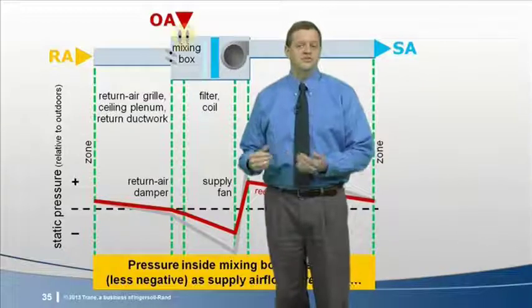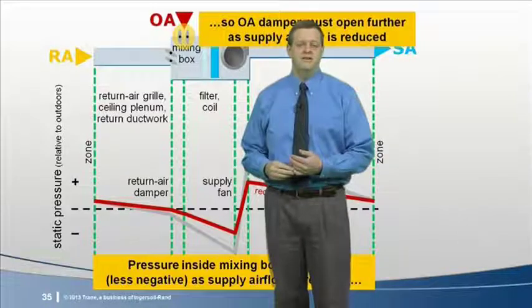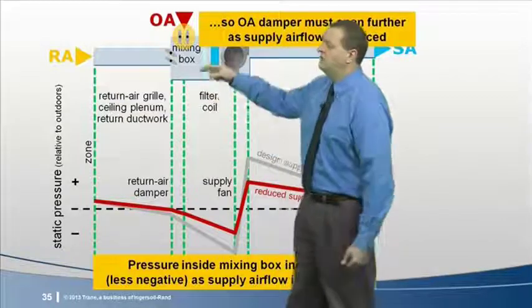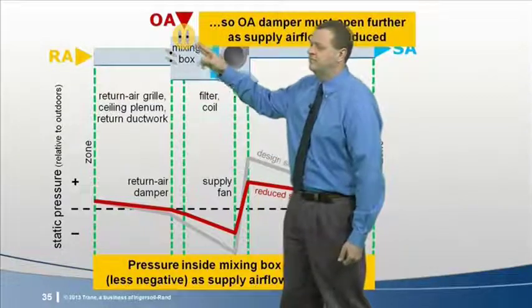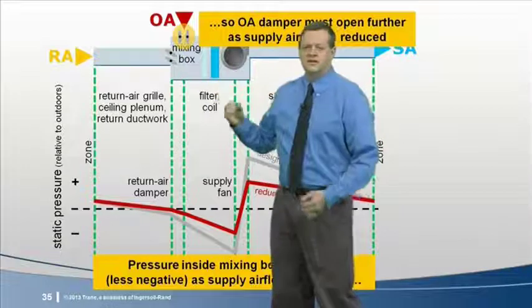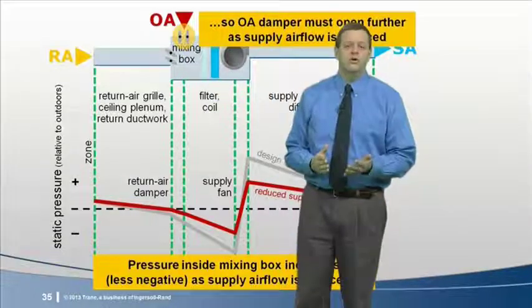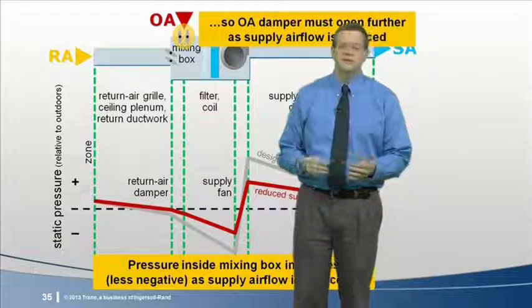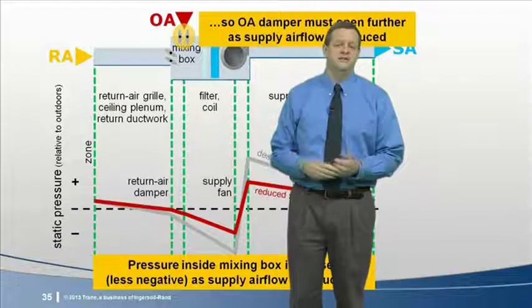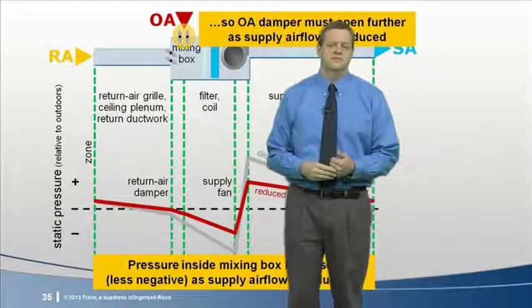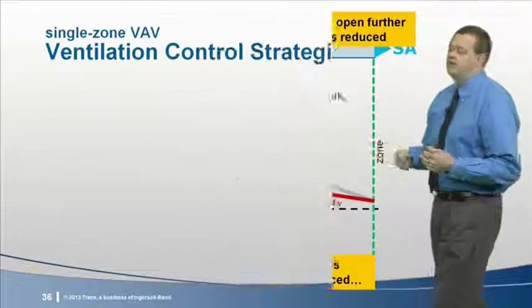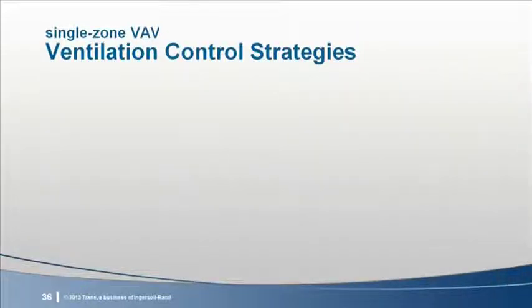So to ensure that the same CFM of outdoor air enters the system, you need to open this damper further when supply airflow is reduced. This requires designing and programming a control sequence that was not necessary with a traditional constant volume system. Now, while there are others, I'll describe a few approaches that might be used to address this issue and ensure proper ventilation in a single-zone VAV system.